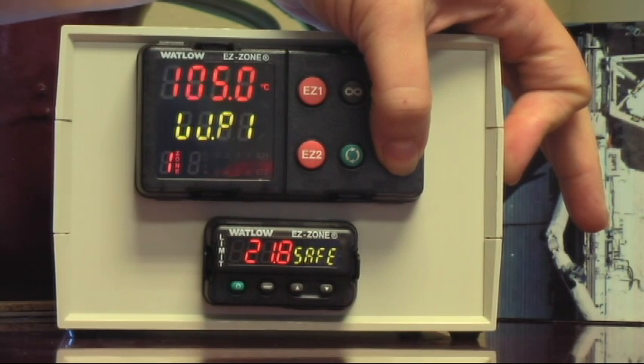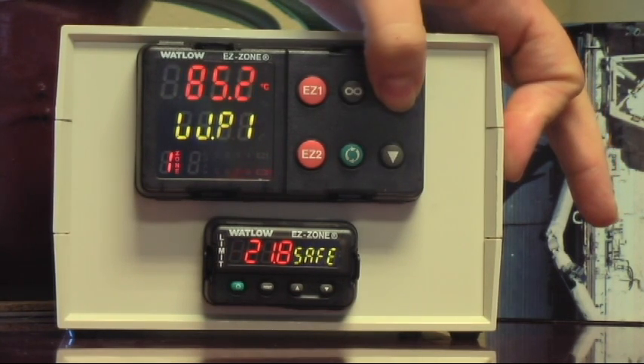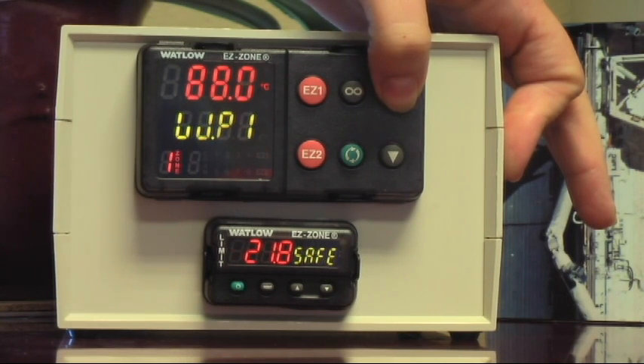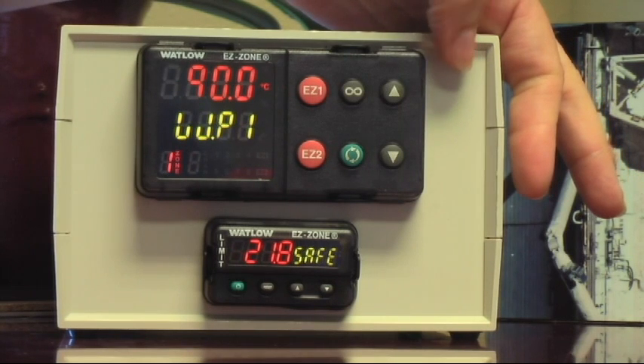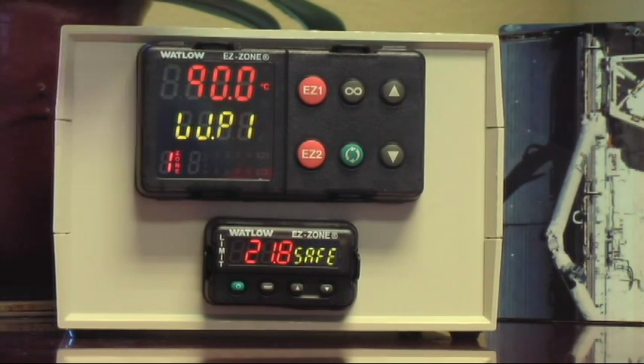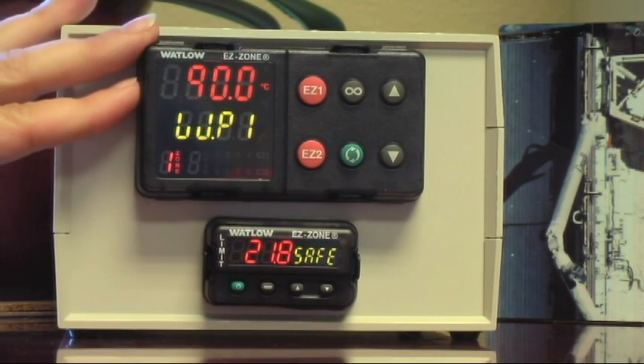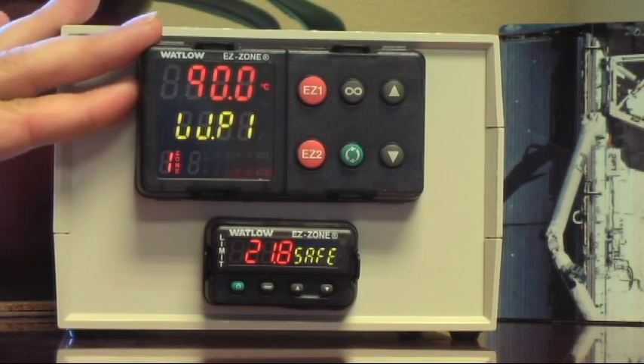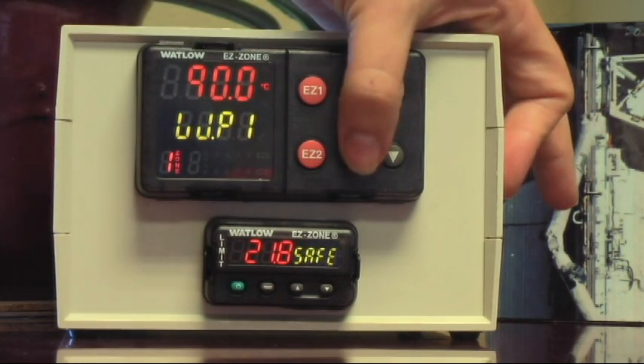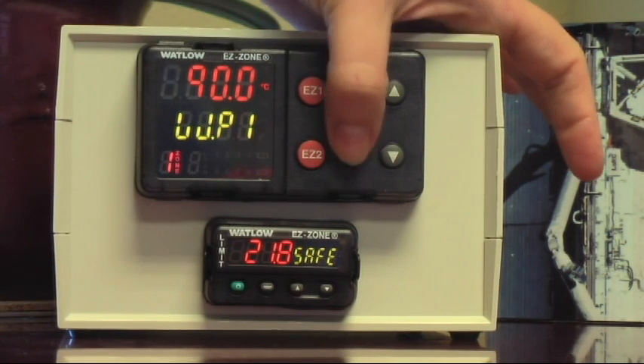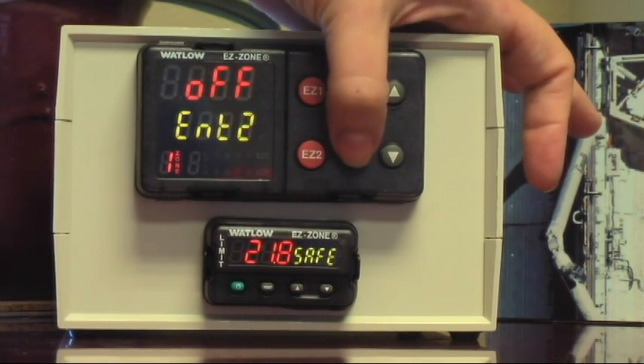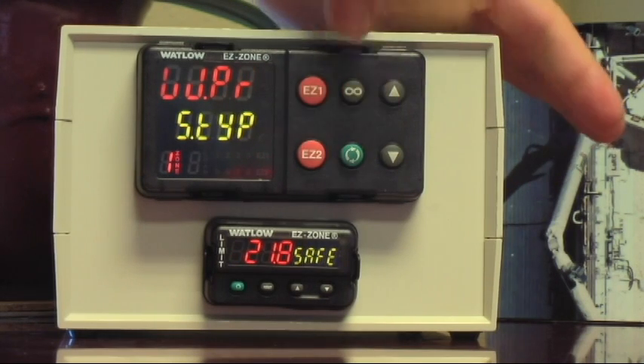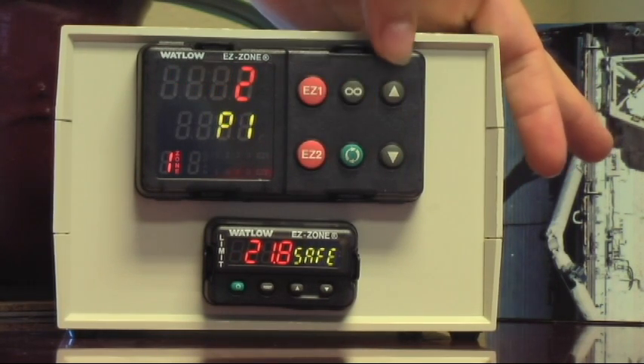This is going to give the controller a chance to get very close to the set point. But if we say wait for a hundred degrees with a vacuum oven, the way it stabilizes so slowly, you could be at 99 for a long, long time. So we're going to say wait for 95 degrees. And when you get there, start the timer for Mary's parts. Okay. So that's the set point. Got it. Green button and ENT one and two are both off. Infinity key.